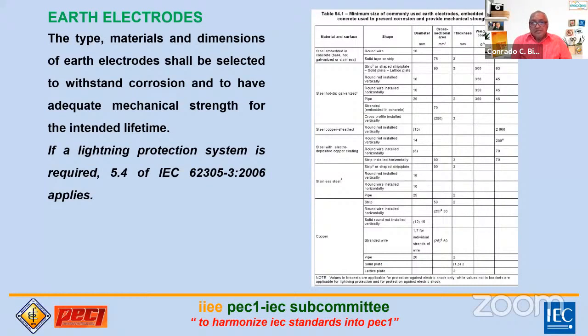So on the right there's a table showing the different materials being used in IEC. Very common is steel embedded in concrete, bare or hot galvanized or stainless steel. It comes in round wire or solid form. These are the diameters and cross sections, which are minimums, so you can make them bigger if you want.